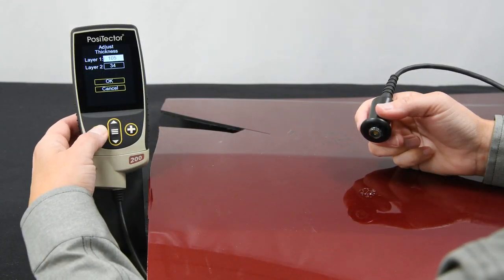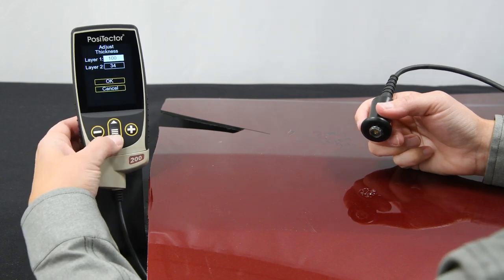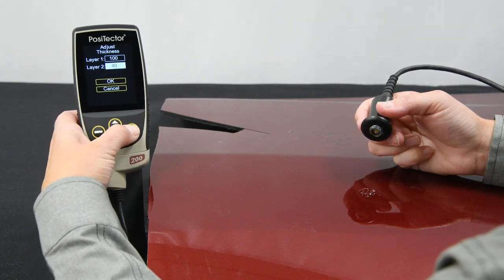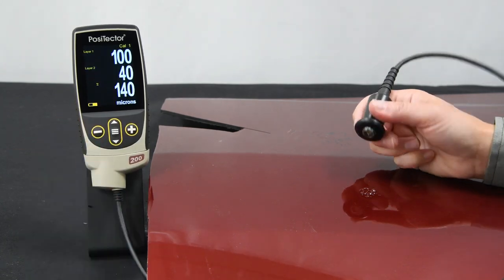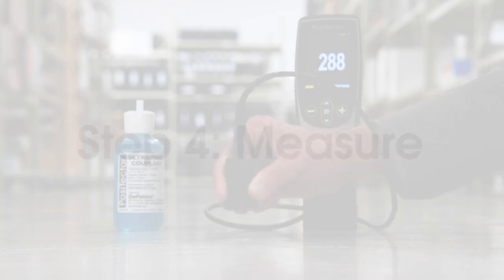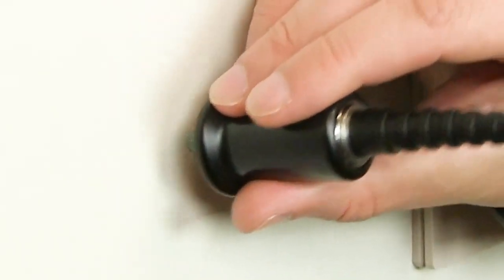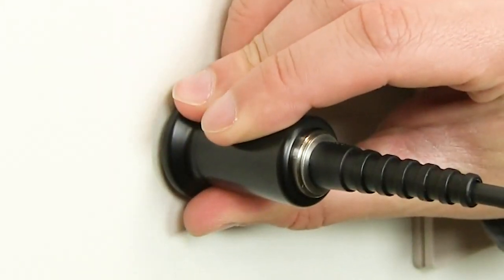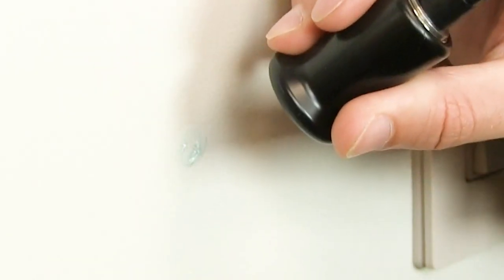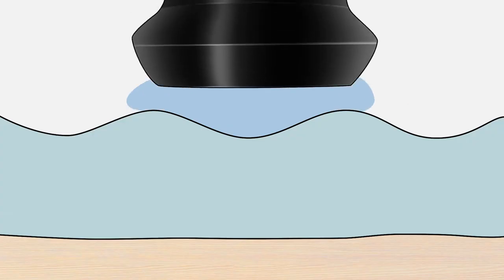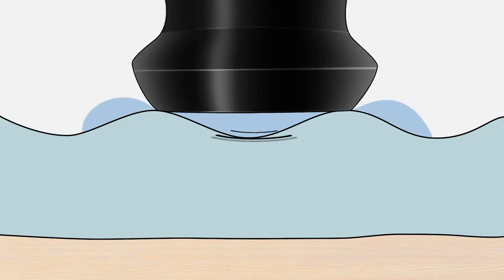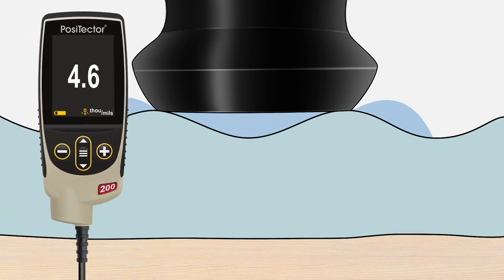For advanced models with multiple layers selected, use the down arrow to select the subsequent layers and adjust as necessary. The Positector 200 is now ready to measure. Simply place the probe onto the coated surface and press down with sufficient pressure to depress the probe housing towards the surface. The instrument sends an ultrasonic pulse into the coating and listens for reflections from the coating substrate or coating-coating interface, quickly displaying the thickness measurement on the display.